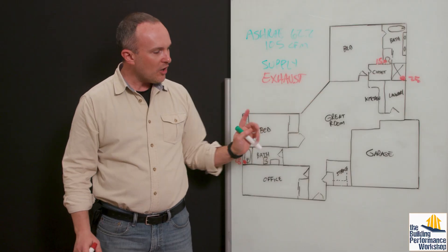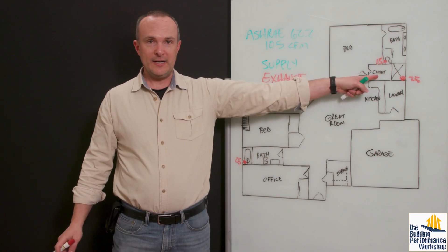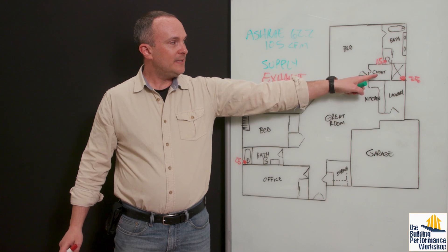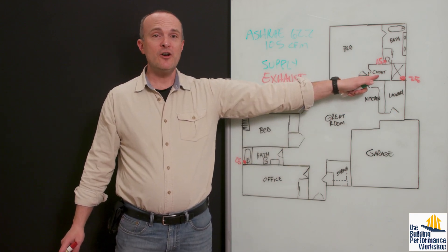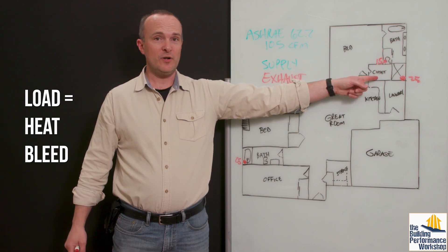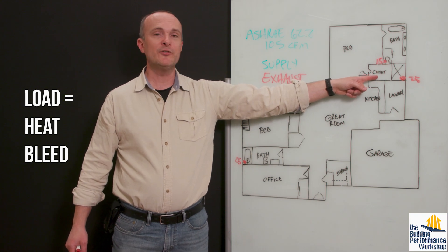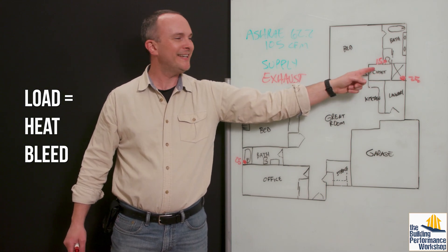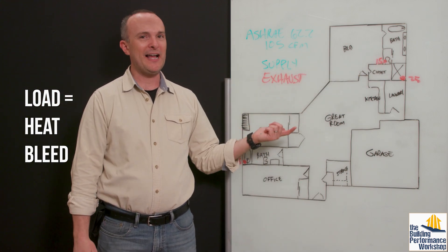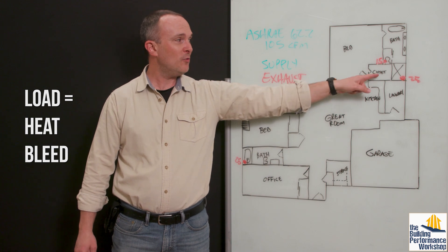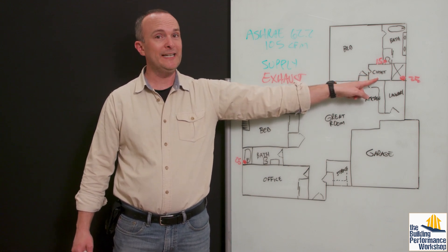So we also have a couple other places that are important to consider. This closet right here, I have described in other videos about this floor plan, has no load. That room has no exterior walls. It has a floor that has no exposed perimeter. It might be under an attic, but it's got no windows in it. And the amount of load that an attic insulation is going to impose on it is not a lot. So it's not going to bleed a lot of heat. Therefore, there will not be a vent to deliver heating and cooling in this closet.